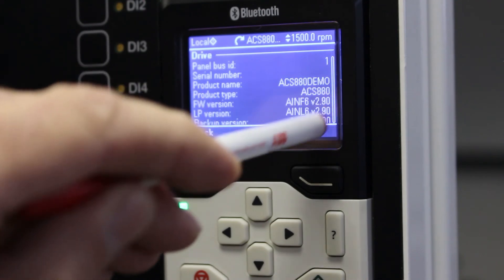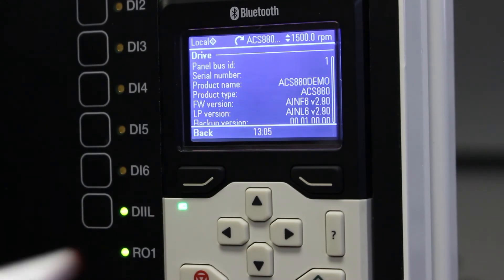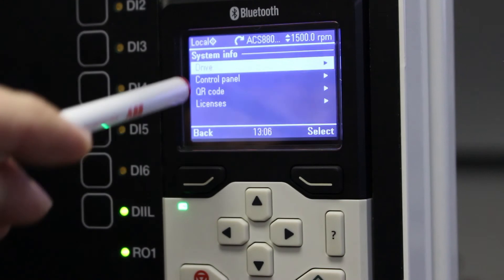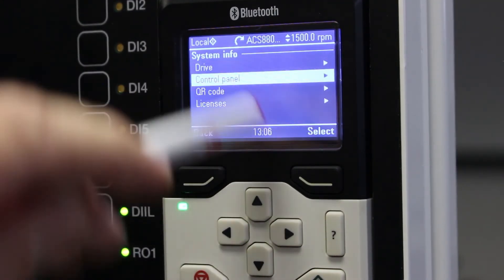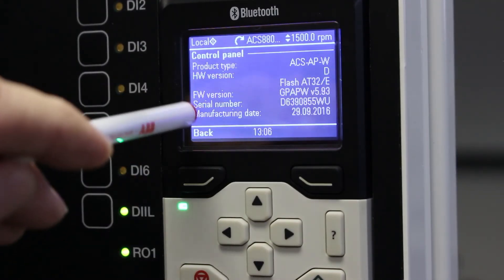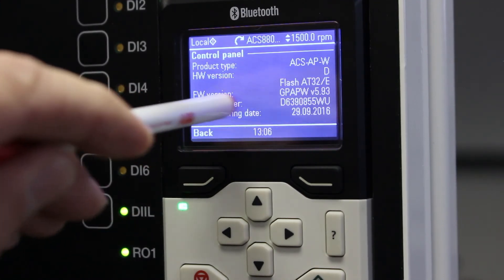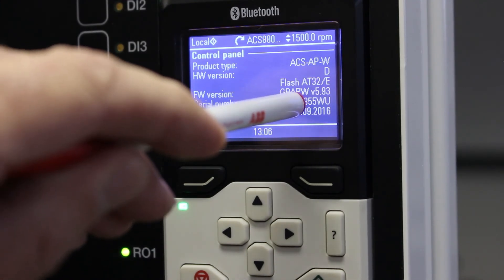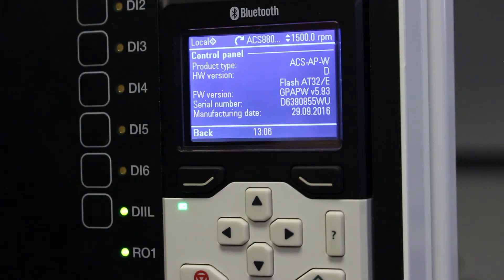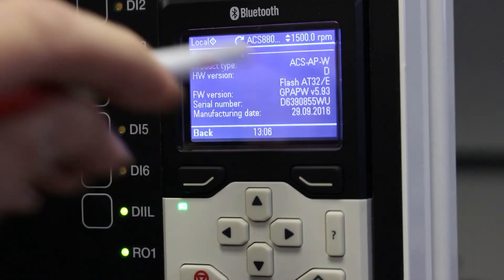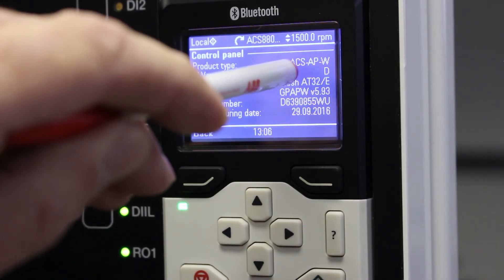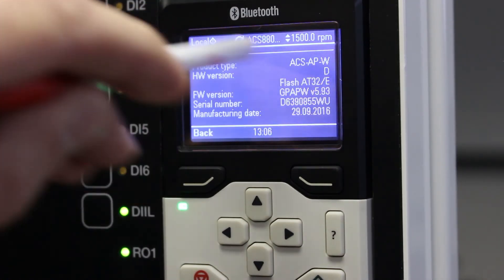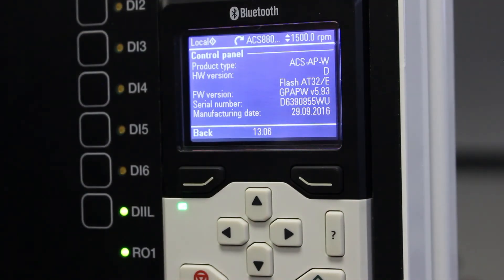This is what we want from you guys when we ask you for the firmware version. Now, if I want a firmware version of the control panel, I can scroll down to control panel, enter it and there I will see firmware version of this control panel is GPAPW version 5.93. Also tells me what is the product type of this control panel over here and this ACS-AP-W means it's a Bluetooth panel for the ACS 880.